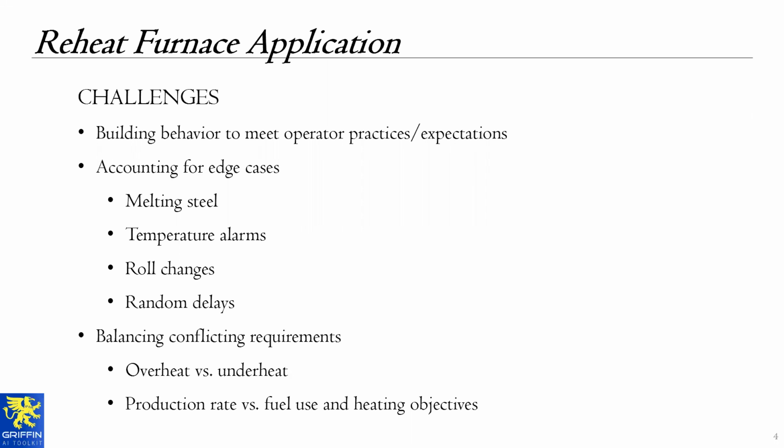And I said, well, I thought we agreed that we weren't going to go over 2,400. Well, that's where the idiosyncrasies and the day-to-day practices of operators can diverge from the engineering staff and other personnel that you might be interacting with. So they were telling me that, no, that's normal. We put it up to 2,440, especially if we're falling behind or whatever like that.